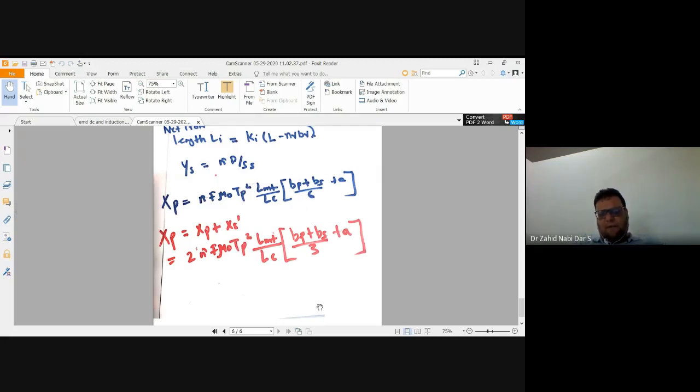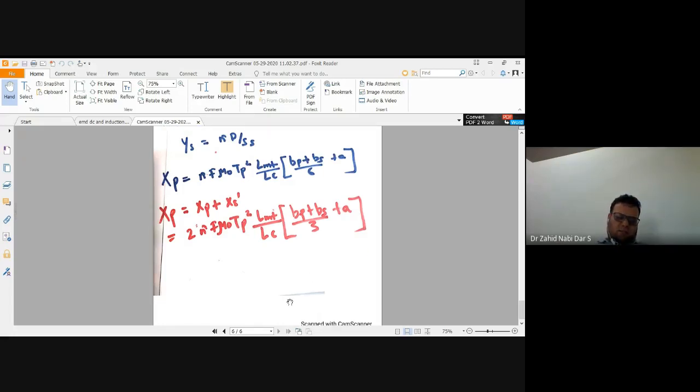Usually what will happen, your transformer is connected for a double circuit arrangement, not single circuit, because our transmission lines are double circuit. If something happens with one phase or one line, one set of line would mean R, Y and B. If you are seeing the towers, when you are moving, you will see instead of 3 wires, you will see 6 wires plus an overhead neutral, so it would be totally 7 wires.